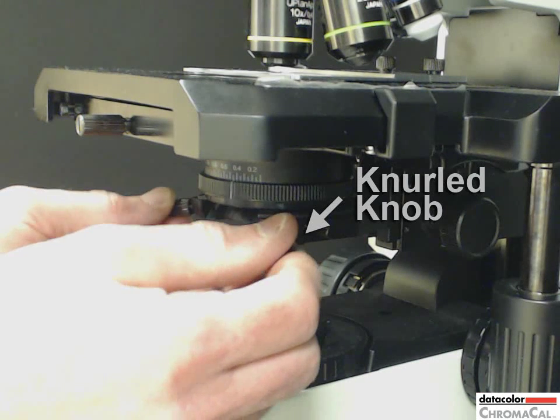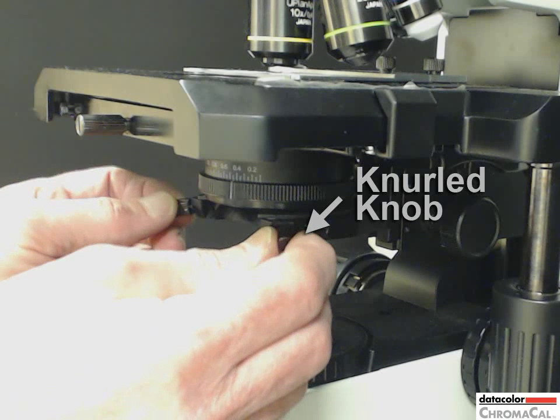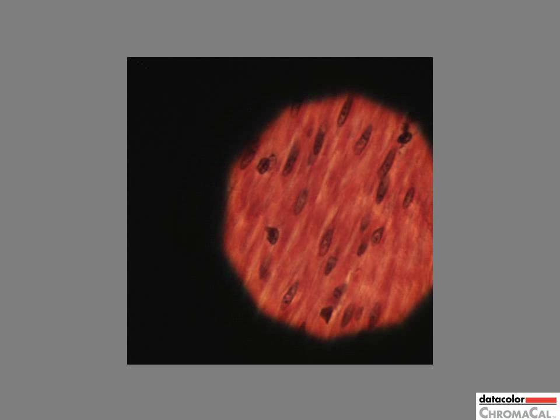Finally, if the field diaphragm blades are not centered, use the knurled knobs to center the shadow image. Here's what you'll see on the microscope.